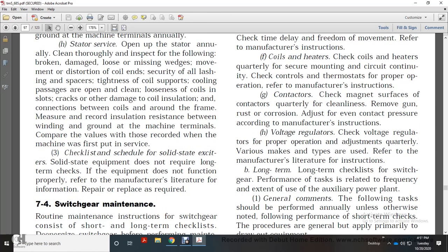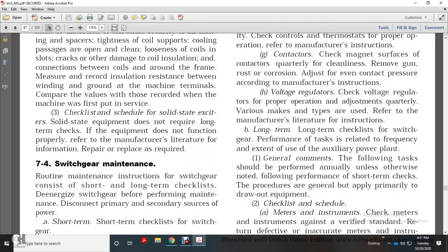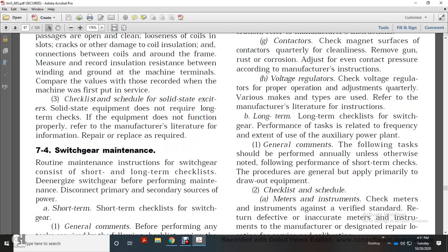Voltage regulator: check the voltage regulator for proper operation and adjust quarterly, per the preferred manufacturer literature and instruction. Long-term checklist: switchgear performance tasks related to the frequency extent with the auxiliary power plant. General comment: the following tasks should be performed annually unless otherwise noted. The following should be performed with the short-term check, and generally apply primarily to draw-out equipment.